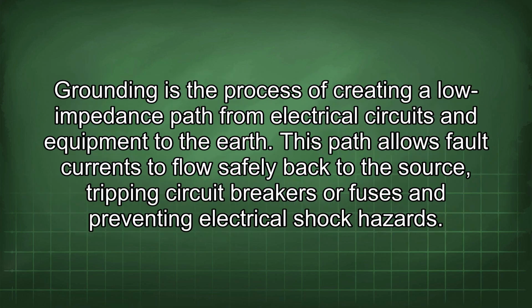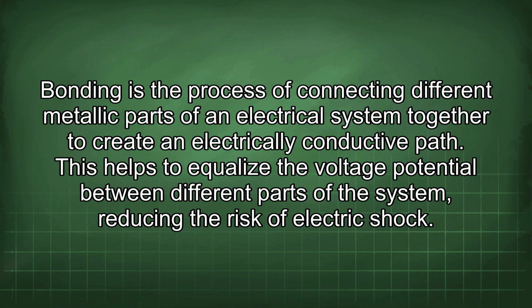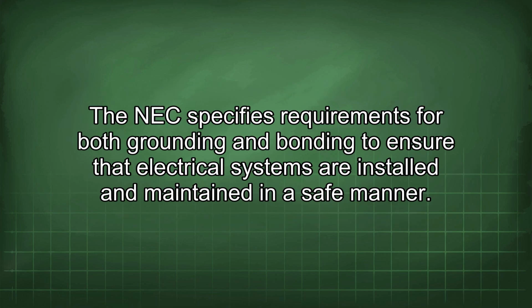Grounding is the process of creating a low impedance path from electrical circuits and equipment to the earth. This path allows fault currents to flow safely back to the source, tripping circuit breakers or fuses and preventing electrical shock hazards. Bonding is the process of connecting different metallic parts of an electrical system together to create an electrically conductive path. This helps to equalize the voltage potential between different parts of the system, reducing the risk of electric shock.